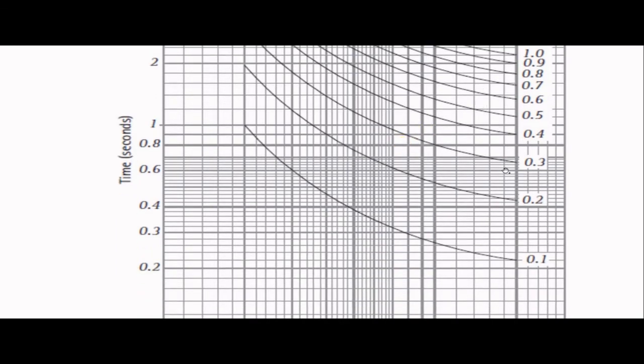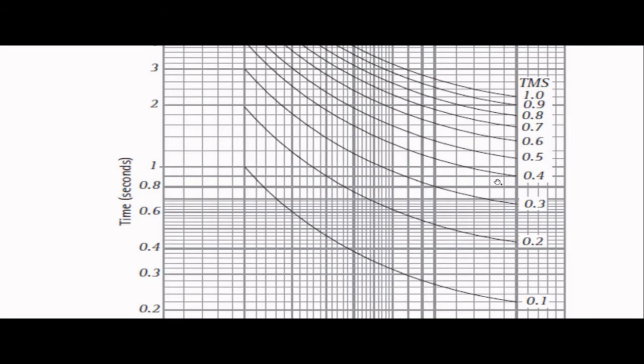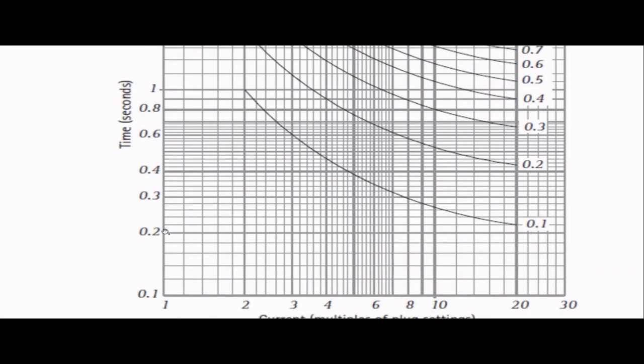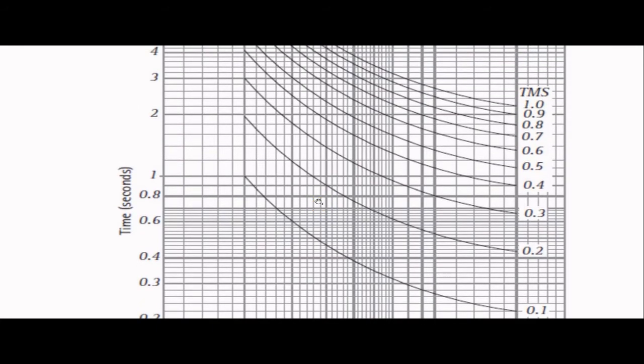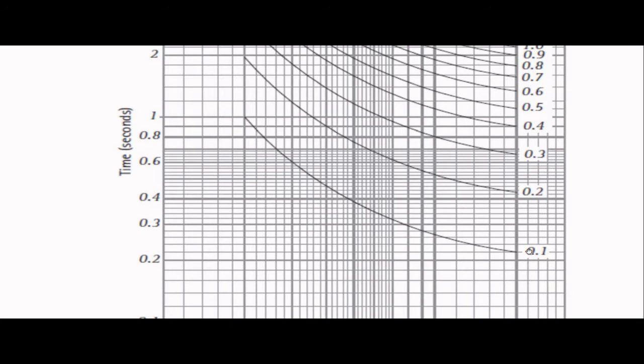But in some applications this 2.2 seconds is very high. Within this 2.2 seconds, everything gets damaged due to the very high amount of current. So how do we control that time? That's why a total of 10 settings are there. If we set the time multiplier setting to 0.1, then it requires only 0.22 seconds. That is below one second, or we may say this is the instantaneous time. The relay detects the fault instantaneously, or at 0.22 seconds the relay generates the trip signal. So based on the application and the apparatus where we want to install the relay, sometimes we set the time multiplier at 1.0, or sometimes at 0.1. It depends upon the user, the application, the apparatus or the nature of protection.